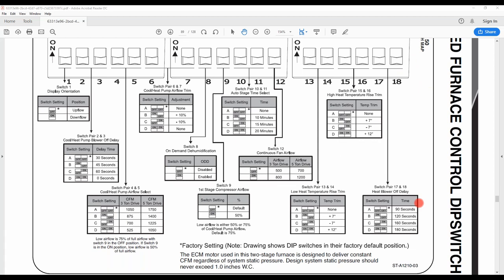17 and 18 is going to be your heat blower off delay. Comes factory set at 90 seconds. You have the option to go into 120, 160, and 180. Just note there that rarely ever do I see that changed from 90 unless you're experiencing any kind of issues or you want to get more heat out of that heat exchanger. You can increase that blower off time delay.